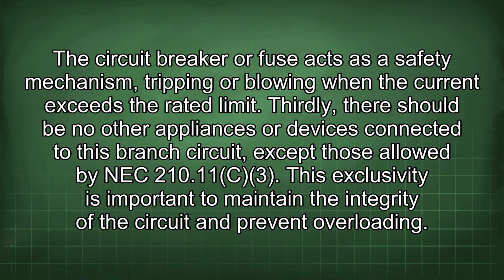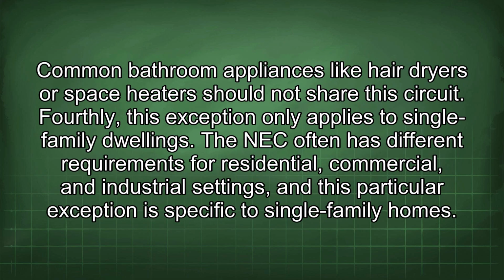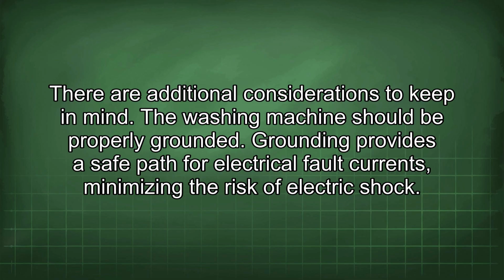Thirdly, there should be no other appliances or devices connected to this branch circuit except those allowed by NEC 210.11c3. This exclusivity is important to maintain the integrity of the circuit and prevent overloading. Common bathroom appliances like hair dryers or space heaters should not share the circuit. Fourthly, this exception only applies to single-family dwellings. The NEC often has different requirements for residential, commercial, and industrial settings, and this particular exception is specific to single-family homes. There are additional considerations to keep in mind.